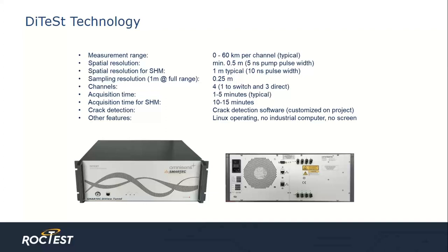These are the specifications of the DiTeSt interrogator for distributed strain and temperature monitoring. The accuracy of the instrument is given by the setting of the unit — that is, how the instrument is configured for measurements. The instrument setting considers four variables: acquisition time, spatial resolution, absolute accuracy, and measurement range. These four variables are interdependent, and accuracy, for example, is the result of the setting of the other three variables. In the literature, we always mention the accuracy of 20 microstrain as a typical value, but this can vary according to the measurement setting.